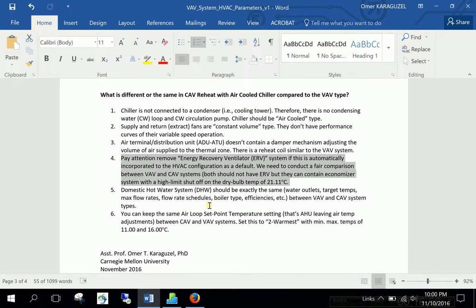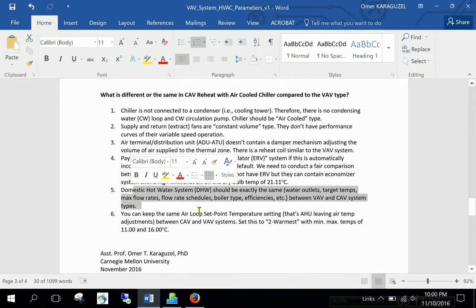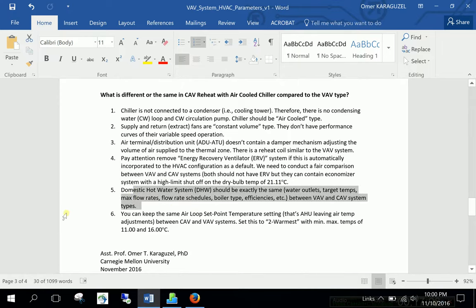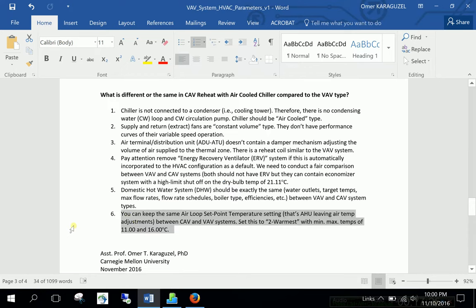And don't forget to change, incorporate an economizer. You should incorporate an economizer. And change the economizer high limit shutoff dry bulb temperature 21.11 degrees. How about domestic hot water system. Exactly the same. I am emphasizing this. The water outlets. The target temperatures. Max flow rates. Flow rate schedules. Boiler type efficiencies. And everything. Between VAV and CAV. They should be the same. No change. To keep the game as a fair condition.